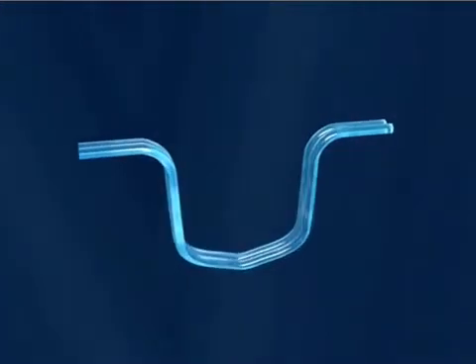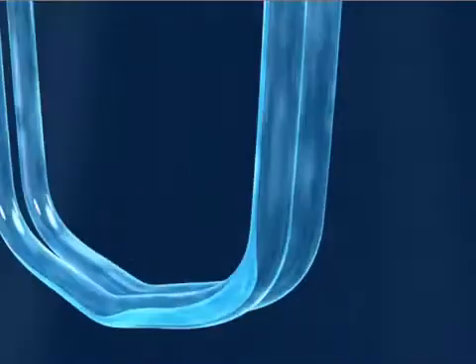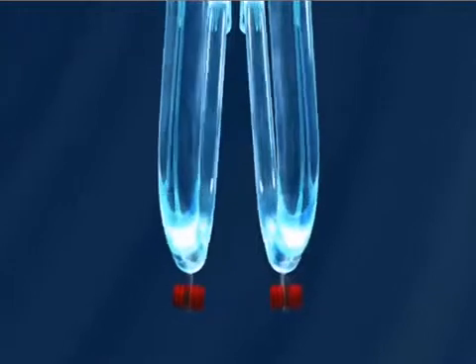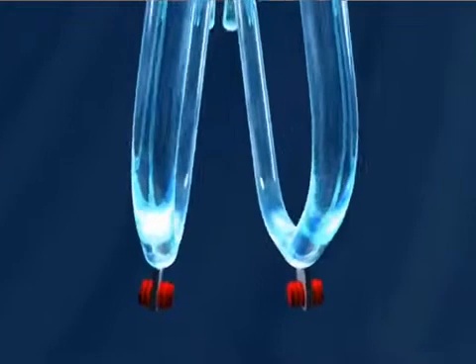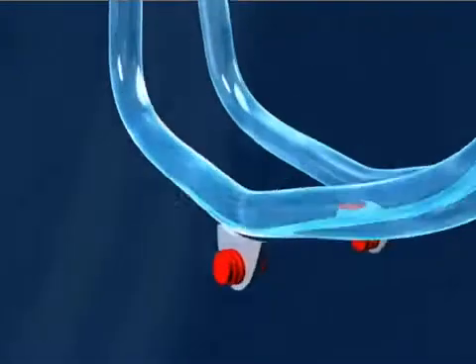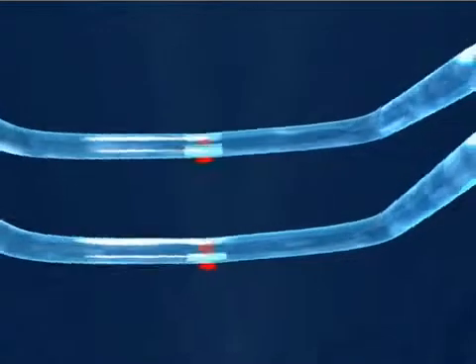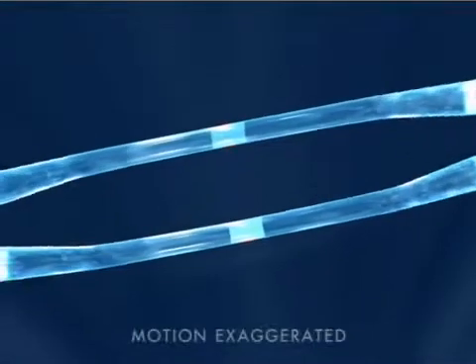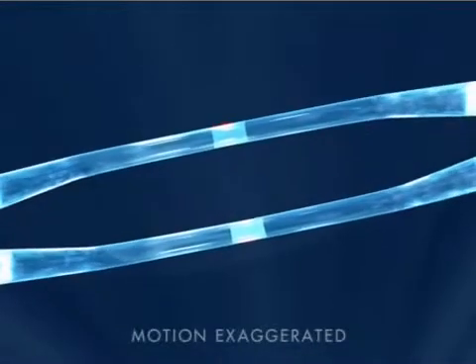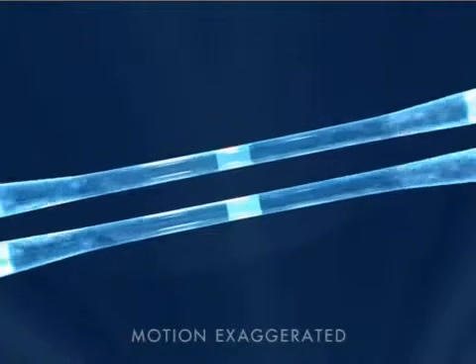For practical exploitation of this principle, it is sufficient for the two measuring tubes to perform oscillations on a small section of a circular path. This is achieved by exciting the measuring tubes with an electromagnetic exciter in its first resonance frequency. When no mass is flowing, the two tubes oscillate symmetrically.